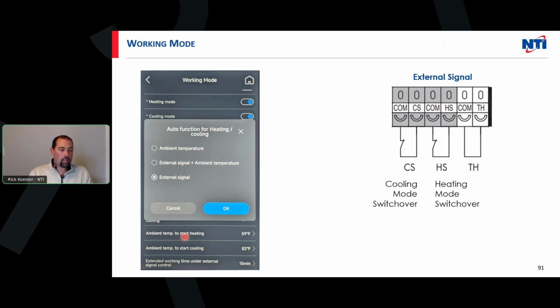If it's just watching outside temp, as you can see down below, our start temp for heating and cooling. This is not a realistic setting here, but I could say, all right, at 70 degrees, anything above 70, I want this to be in cooling mode, ready to go. I would put 70. Anytime it goes above 70, it's going to be ready to go and standby for cooling. If I put it on 59 or less than 59, it's going to be ready to heat. So the machine will switch, run in those modes when it's less and above those temperatures.